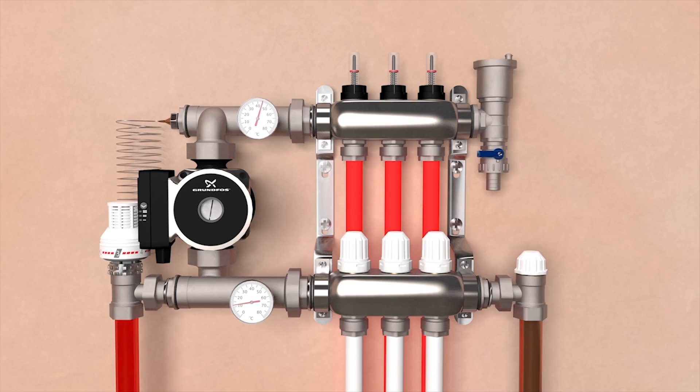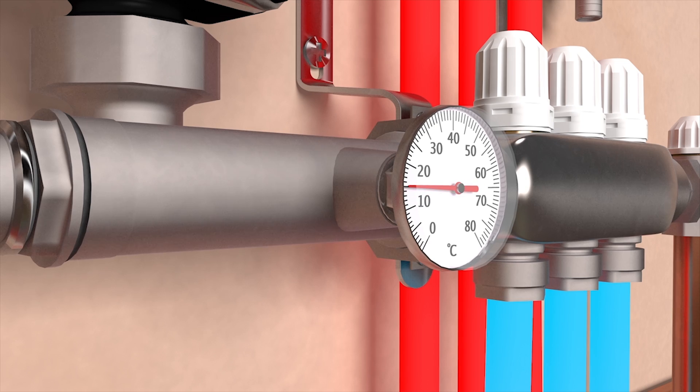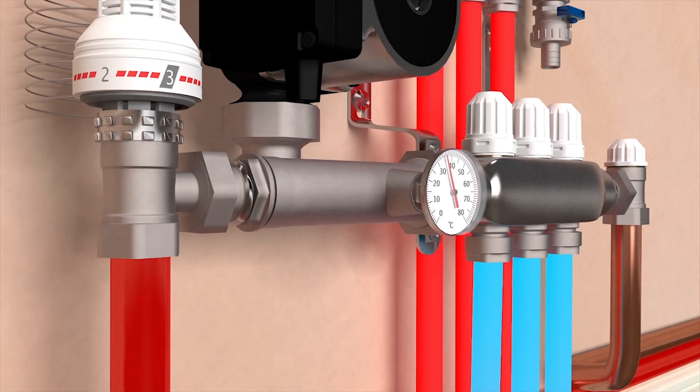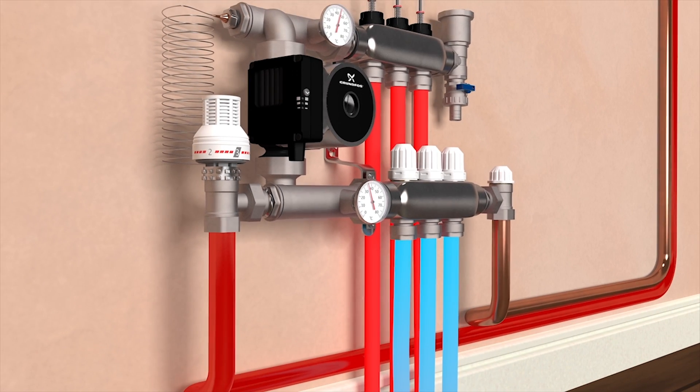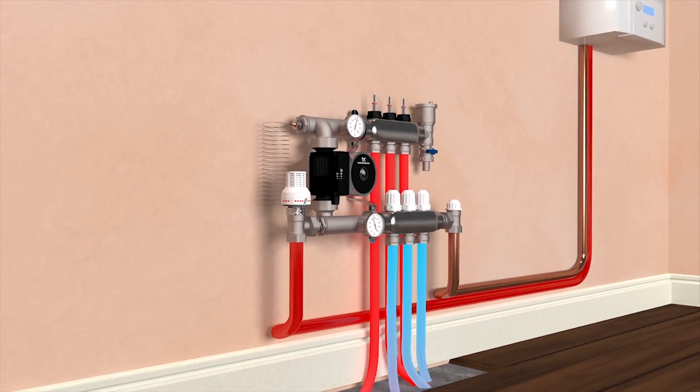Water returns to the manifold from the floor loops into the bottom return bar. The thermometer on this bar will give you an accurate reading of the water returning to your manifold. This is generally some 10 degrees less due to the heat being transferred from the pipes and radiated into your rooms.